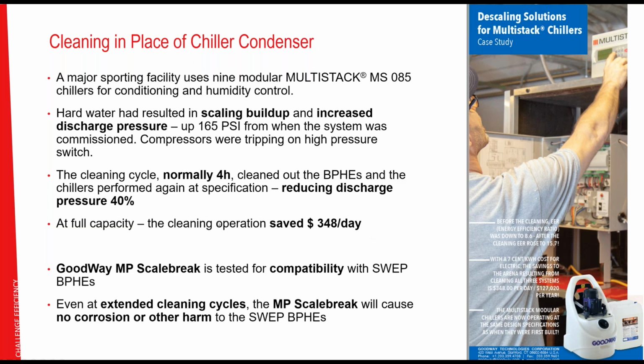According to Tim Forgo of Goodway, a cleaning cycle will normally be 4 hours. In this case, if I'm allowed to say that, they left it overnight because they thought, well, let's leave it overnight. Why stop now and put it back up? So they left it overnight, which is not a problem since we have this tested for compatibility. When they came back and flushed it out, they had reduced the discharge pressure by 40%. They were back at factory specification, and when the system was operating at full capacity, by doing this cleaning in place, they saved $348 a day.